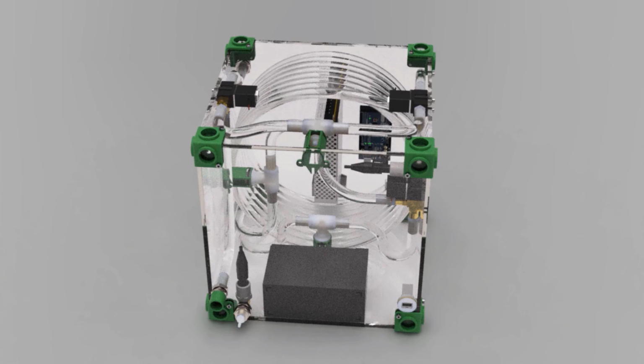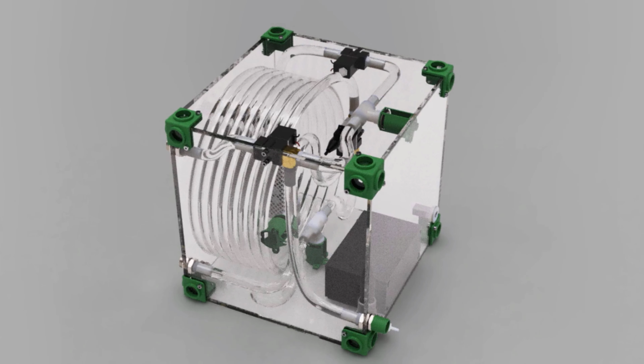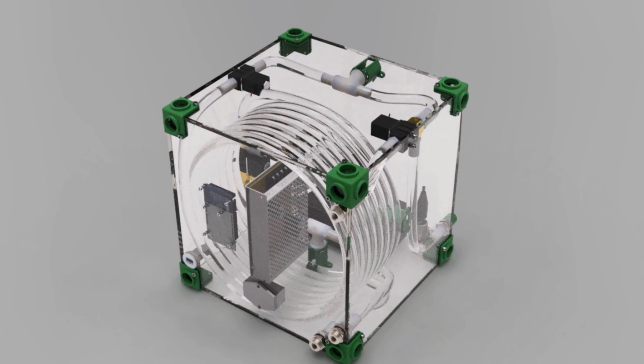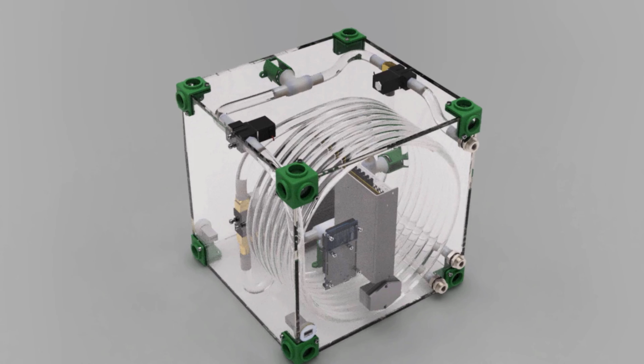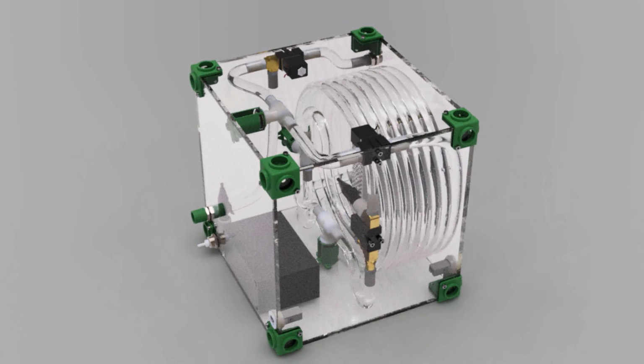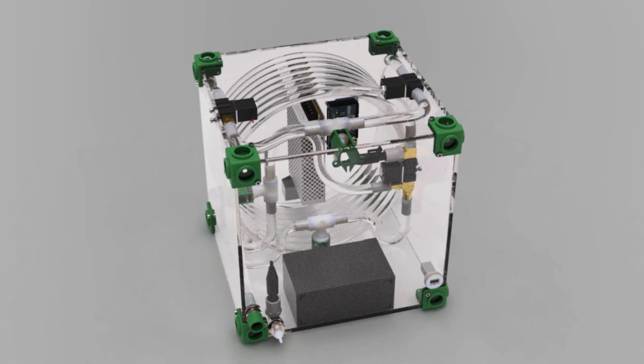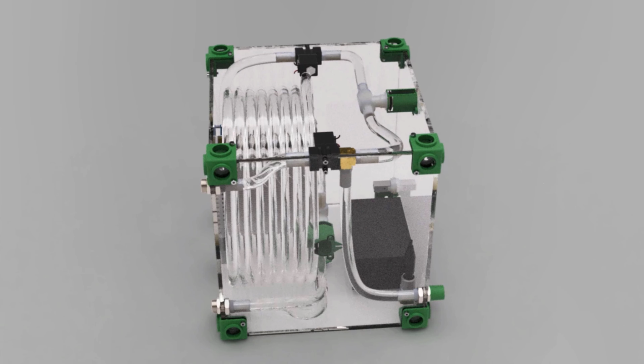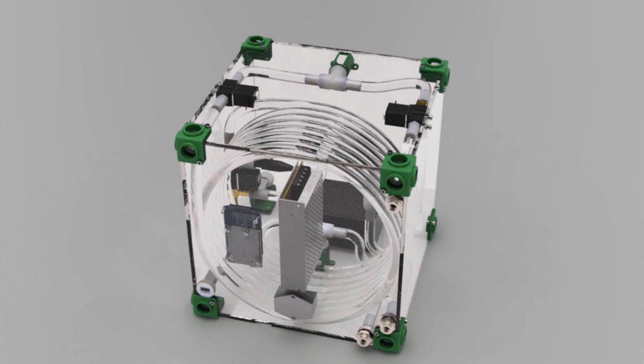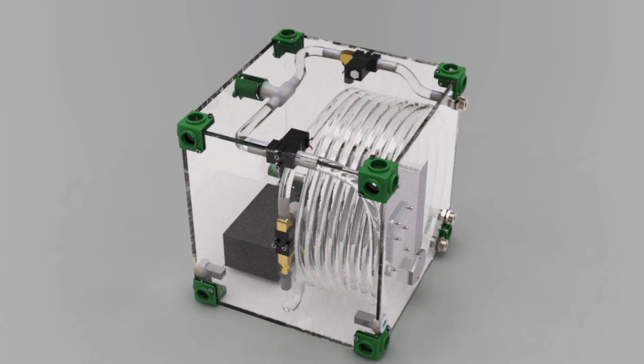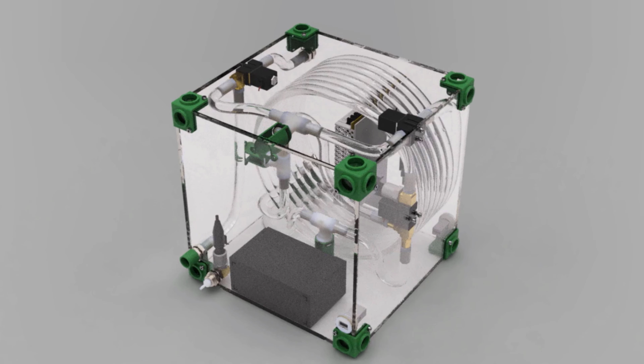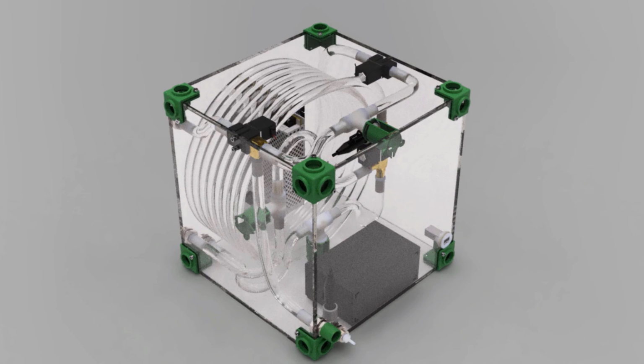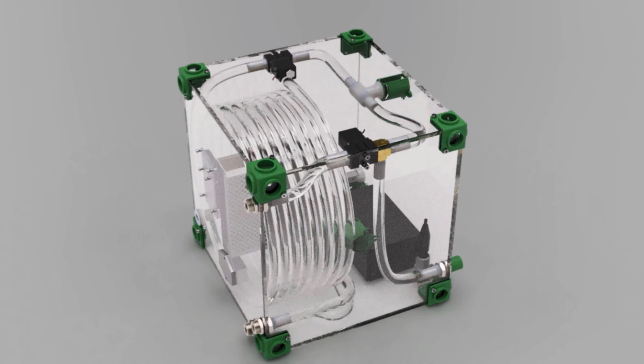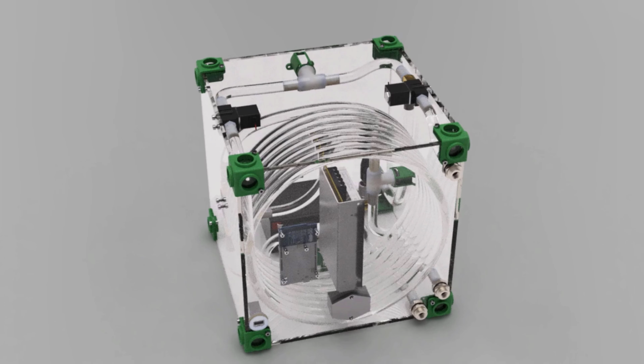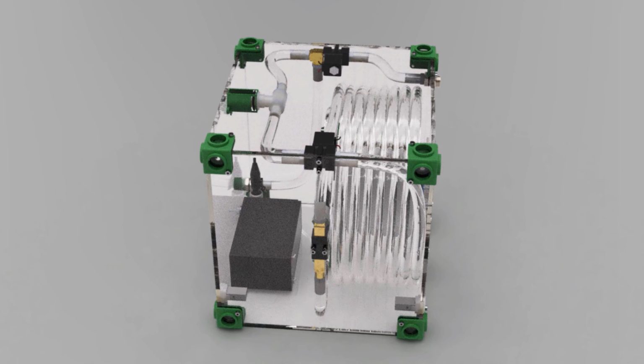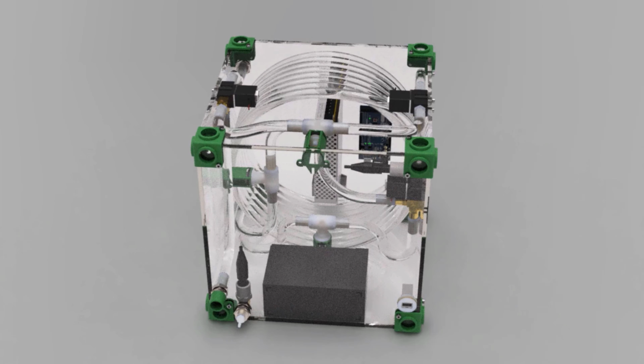So here's the ventilator in its transport configuration. To save production costs and time, standard off-the-shelf parts were used wherever possible. Every pneumatic fitting is the common 1/8 inch NPT. The 3 black solenoid valves are mass-produced. The 3 white proportional flow control valves, or PFCVs, were built from common steppers and needle valves. 1/2 inch vinyl tubing forms the tank and connections. The same metric screw fastener is used throughout. PVC is used to make modular connections. We used Arduino for the control system and a Meanwell uninterrupted power supply.